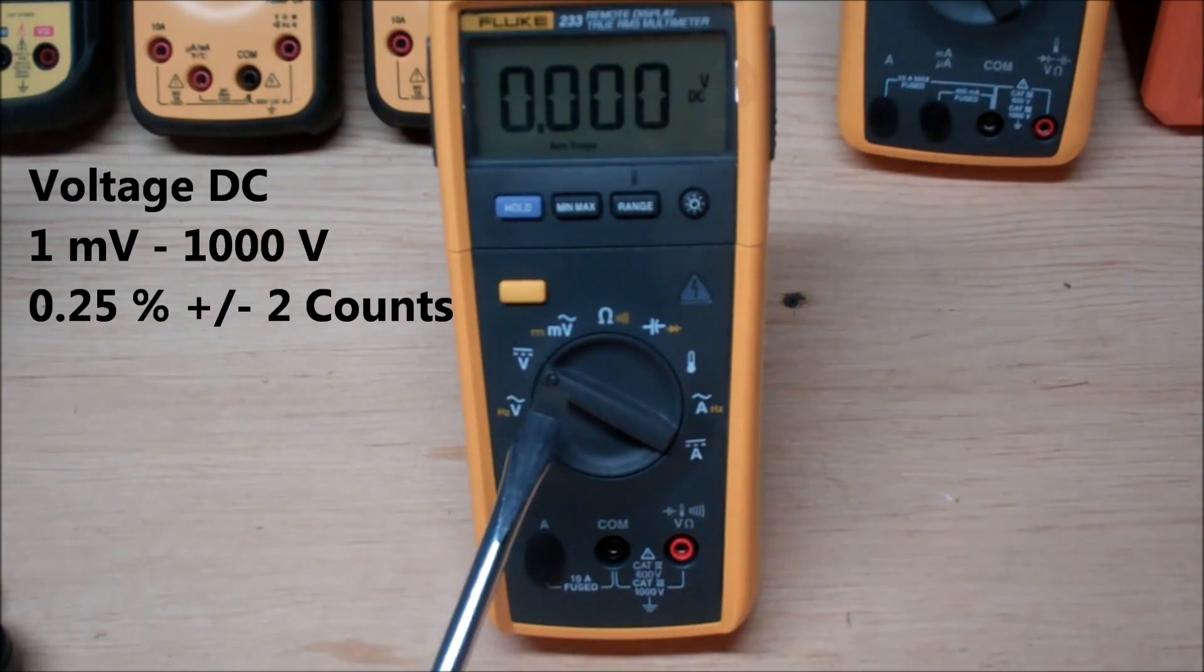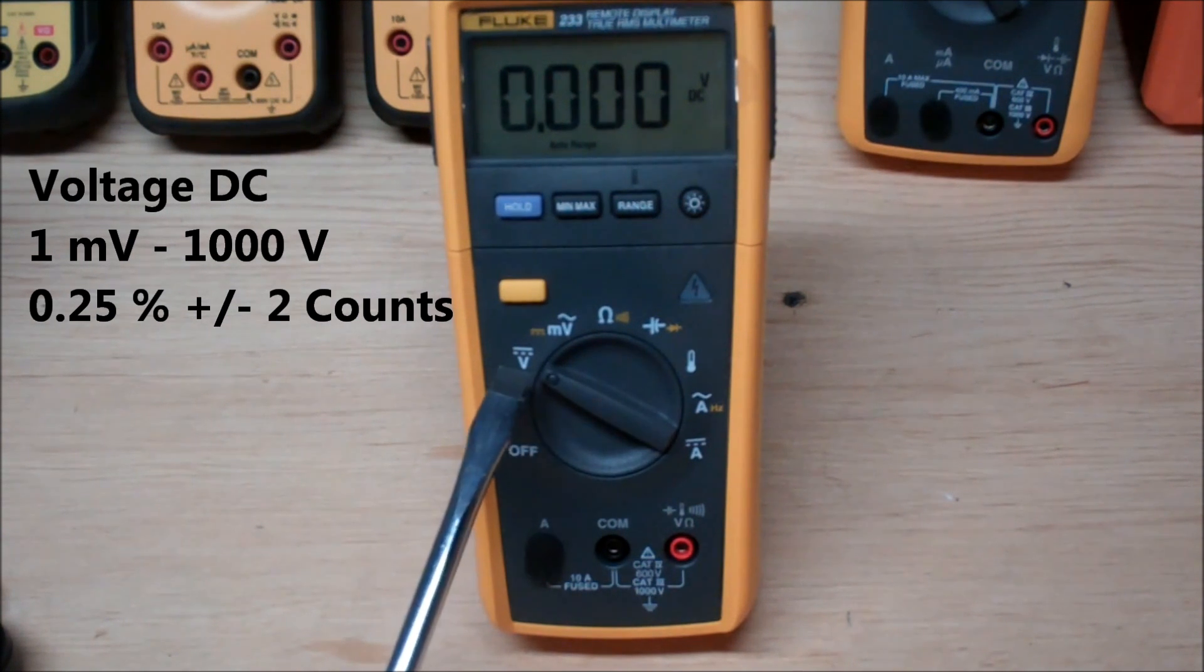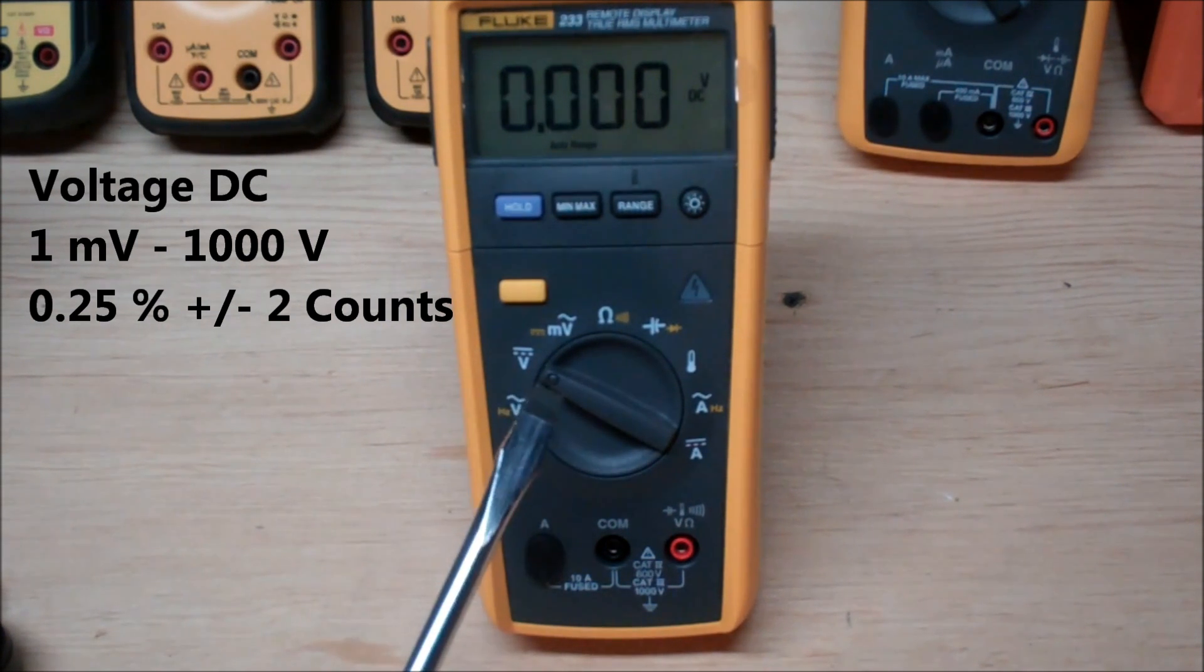Now the DC measurement capabilities of this is a lot more accurate than the AC capabilities as every meter is. It has an accuracy of 0.25 percent plus or minus two counts. And this also has the exact same range of measurements from 0.01 millivolts to 1000 volts DC.